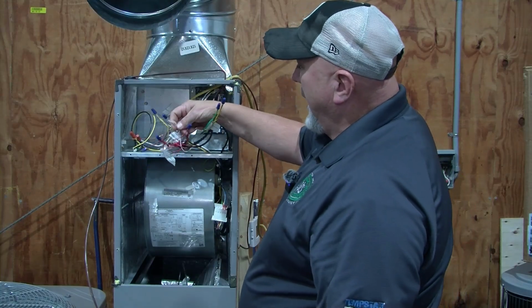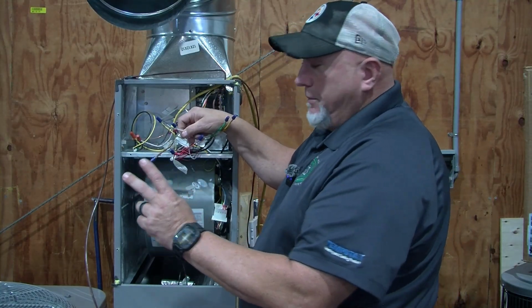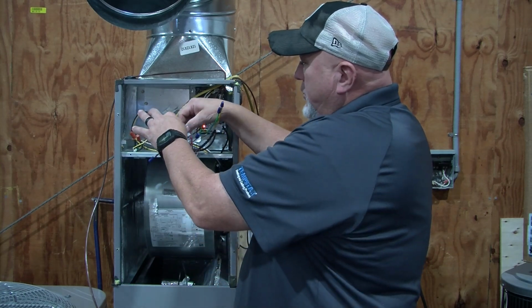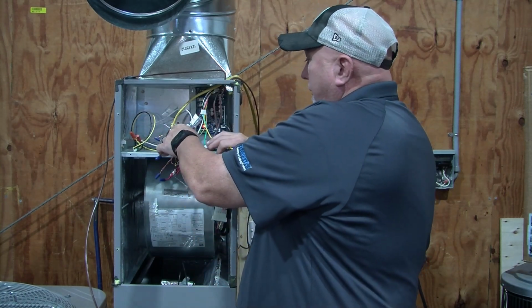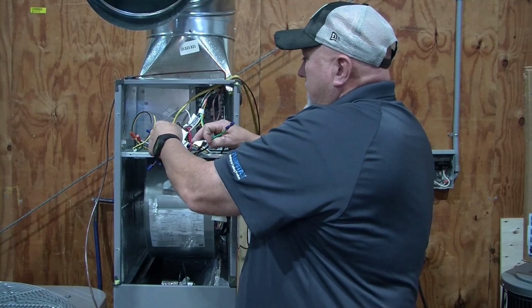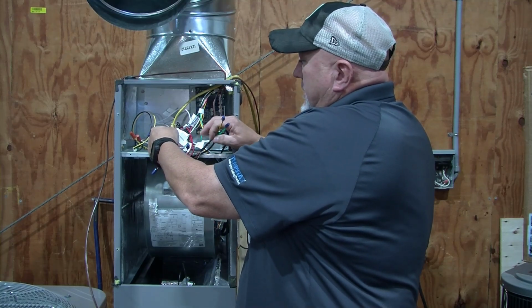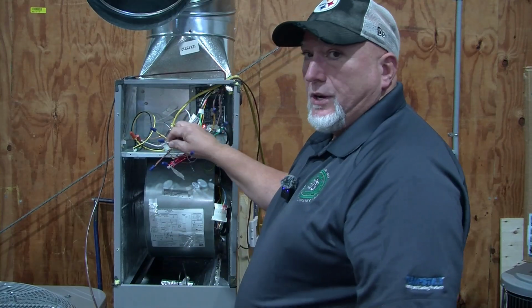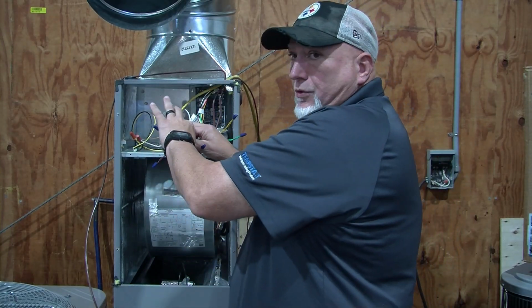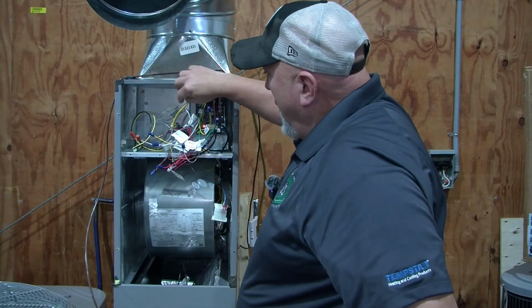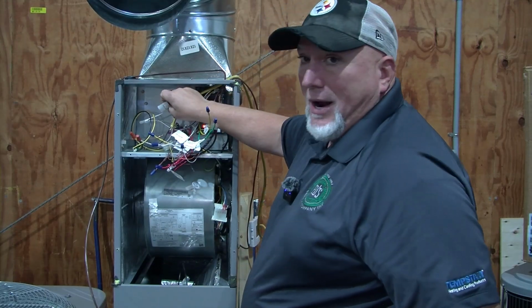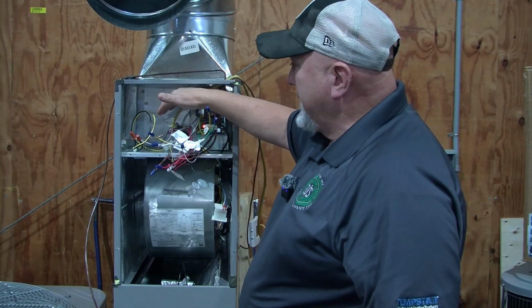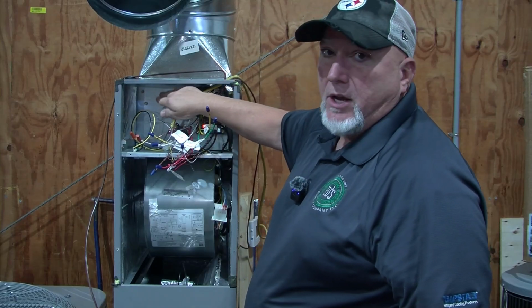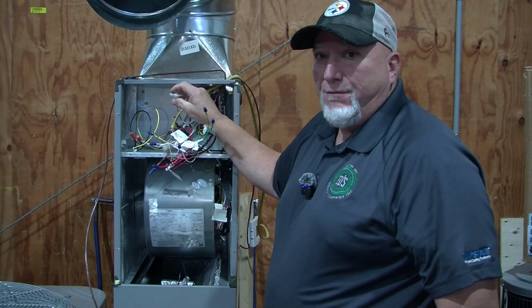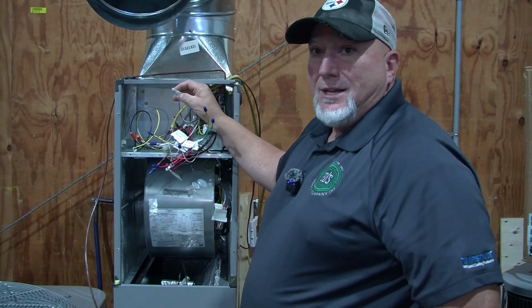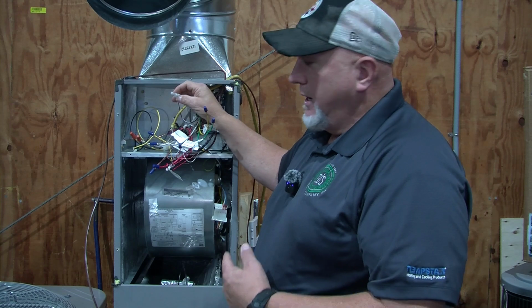And then your white wire, both of them, from the condenser unit and the thermostat, will go to the white here that is labeled white in to thermostat. So your condenser unit and your thermostat will go to this wire here. You do not have to worry about this other yellow wire like you normally would. That's where you would tap into with your thermostat. Do not cut those wires. If it has a factory connection on it, it's made to stay connected, not cut. So keep that in mind.